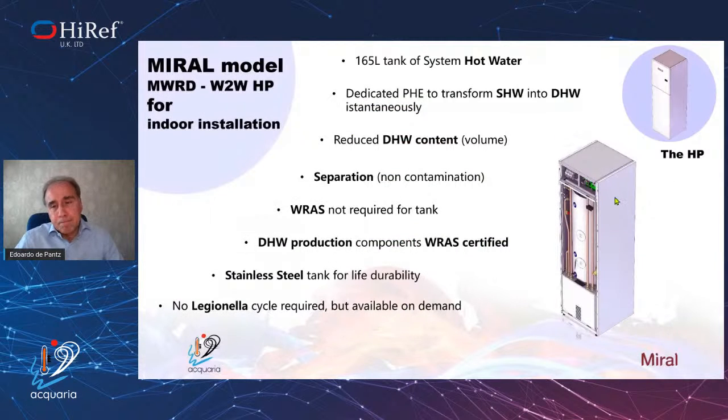So this is the unit. The unit is fully accessible only from the front side, so not from the side or from the back. When you open the front panel, you can see the tank, the 165 liter tank. This tank is for system hot water, so it's not domestic hot water. It's 165 liters fully and exclusively dedicated to technical water.